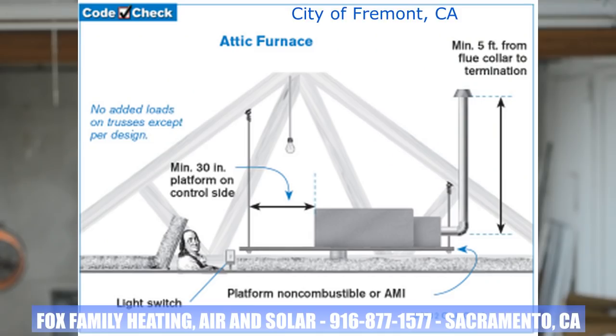The installation manual for our equipment in the attic says clearance in front of the new furnace and coil in the attic is required to be at least 24 inches. If the county inspector adheres to the International Mechanical Code or the California Mechanical Code — which says 30 inches in front of the appliance — but the installation manual says 24 inches in front of the unit, which one's the correct answer? In this instance, the mechanical code is still more stringent on its requirements. So when I hear people say they only need 24 inches in front of the furnace, I know it'll probably fly the inspection, but the inspector could call us on it and ask for a 30-inch surface area in front of the unit. And you need to know that.